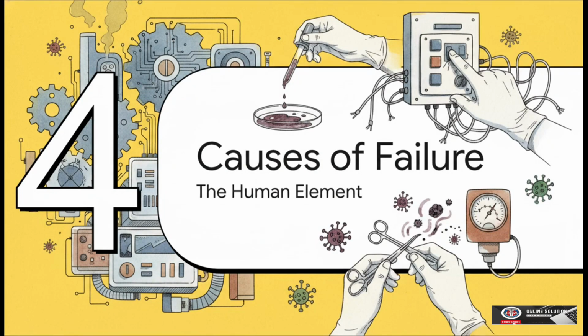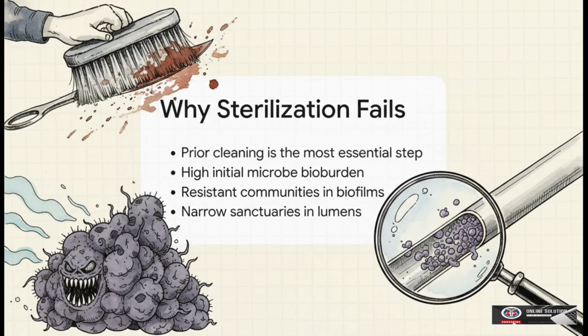But all this amazing tech is totally useless if the human element fails. That brings us to Chapter 4, causes of sterilization failure. Here's the harsh truth. The most expensive sterilizer on the planet will fail if the prep work is sloppy. Prior cleaning? That is your absolute non-negotiable step 1.